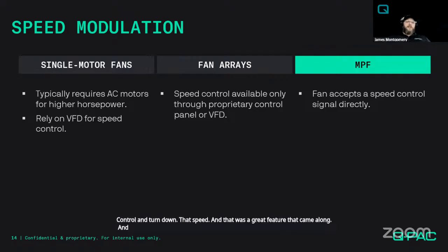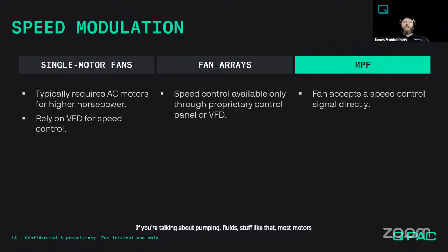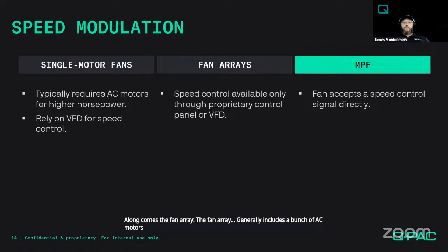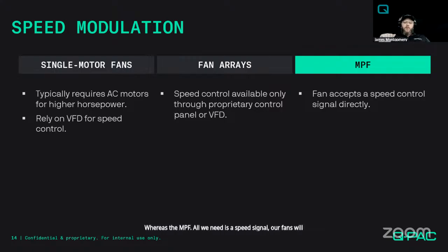And since the advent of that, VFDs have become very commonplace. Almost every AC motor in an application, whether that be HVAC or pumping fluids, stuff like that, most motors are coupled with VFDs now. Along comes the fan array. The fan array generally includes a bunch of AC motors, sometimes different types of motors, all coupled with either one VFD or multiple VFDs for redundancy. Whereas the MPF, all we need is a speed signal. Our fans will run off of a 0 to 10. And if you buy our premium package, you can use our built-in PID loop.